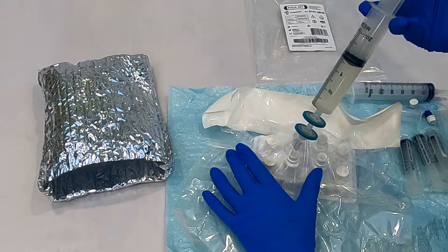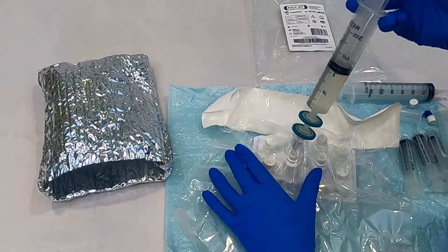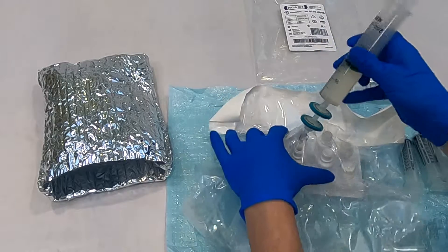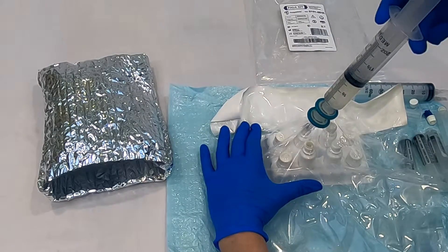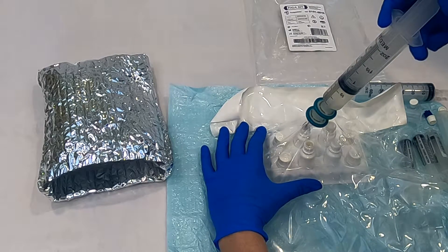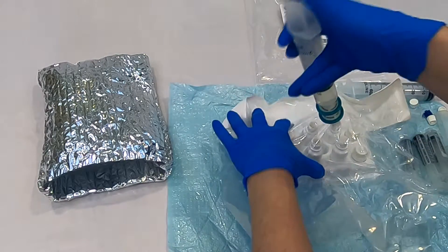The maximum volume of each eyedrop bottle is 11 milliliters. Deliver the solution into each eyedrop bottle, being careful to ensure the delivery nozzle is positioned within each bottle opening. If syringe dispensing becomes too difficult, remove the proximal filter and re-attach the syringe.